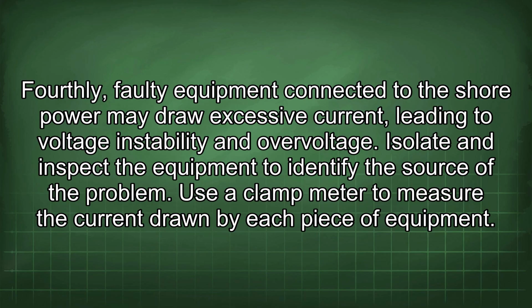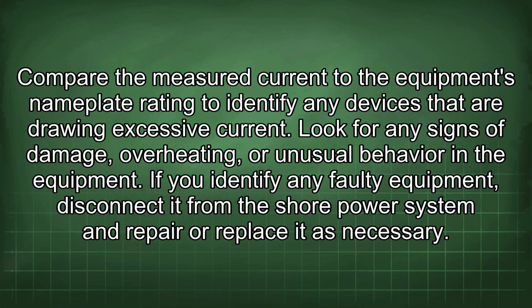Fourthly, faulty equipment connected to the shore power may draw excessive current, leading to voltage instability and overvoltage. Isolate and inspect the equipment to identify the source of the problem. Use a clamp meter to measure the current drawn by each piece of equipment. Compare the measured current to the equipment's nameplate rating to identify any devices that are drawing excessive current. Look for any signs of damage, overheating, or unusual behavior in the equipment. If you identify any faulty equipment, disconnect it from the shore power system and repair or replace it as necessary.